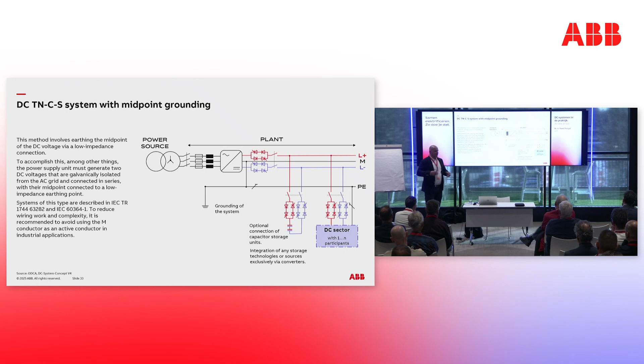For example, in industry applications, they do use these systems, especially in Germany, but with the midpoint ungrounded. When we discuss some other applications that use very specific power supplies designed for 400 volt DC—now I'm thinking maybe about data centers—they will tell you they want the midpoint loadable, because they want to connect their power supplies plus to neutral or minus to neutral. So you can have the 800 volt system but still use the existing power supplies. This is a recurring topic in DC installations: what voltage do we choose?